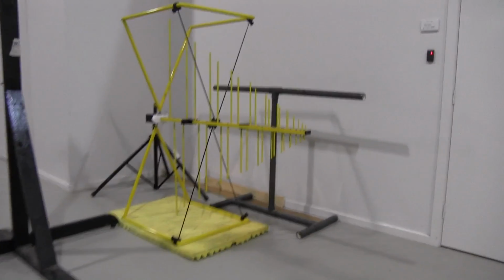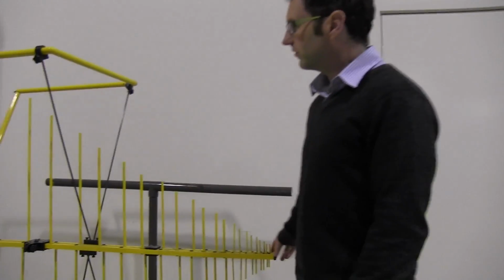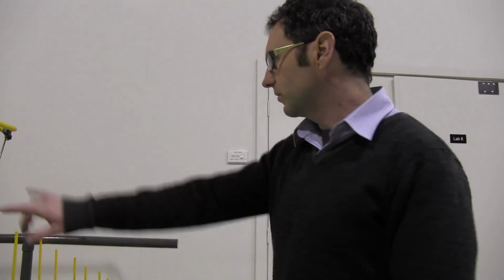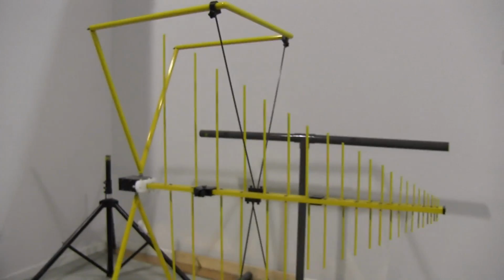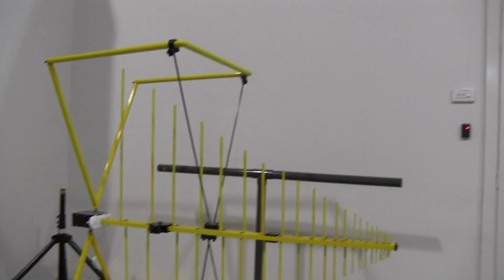So Rob, these are your typical wideband antennas you would use for testing? Yeah, that's right. We use these ones for immunity testing. So we put a signal into it and test a product for susceptibility. So this is basically a transmitting antenna. Can they have dual use? We haven't calibrated these ones for emissions, for receiving. But there's no reason why not.